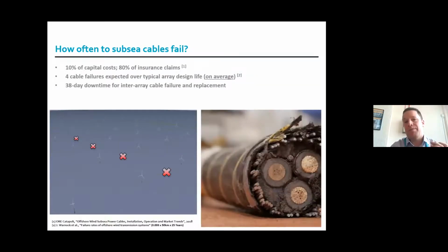These cables, probably very well publicized, aren't particularly reliable. They fail a lot, certainly in proportion to the capital cost. For example, if you had a wind farm like this over a lifetime, you might expect on average about 4 cable failures—a very high failure rate, fairly significant downtime, because ultimately this is what carries your power, so there's quite a big consequence if you can't send that power back to shore.